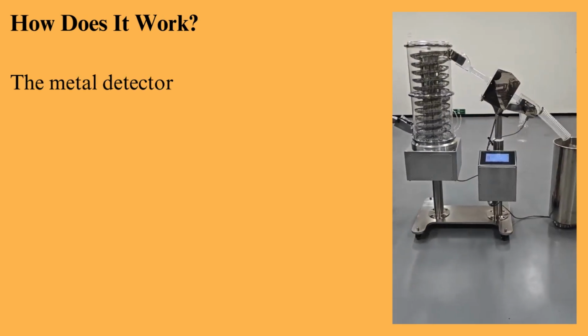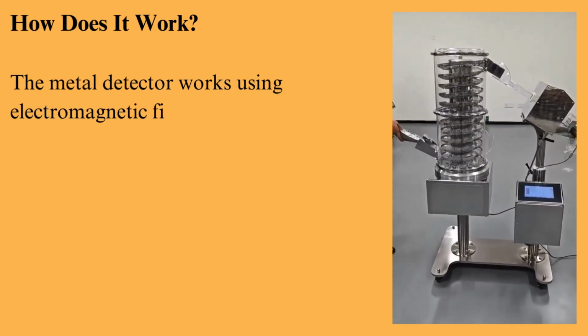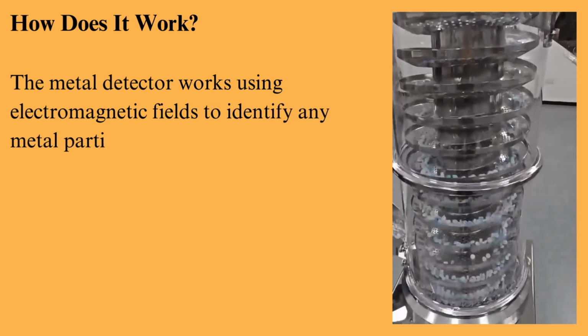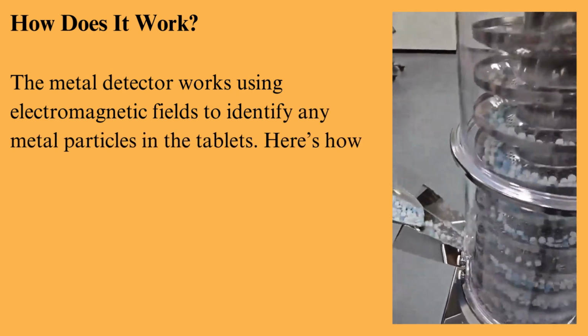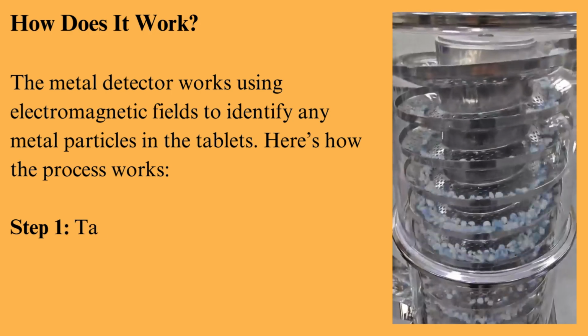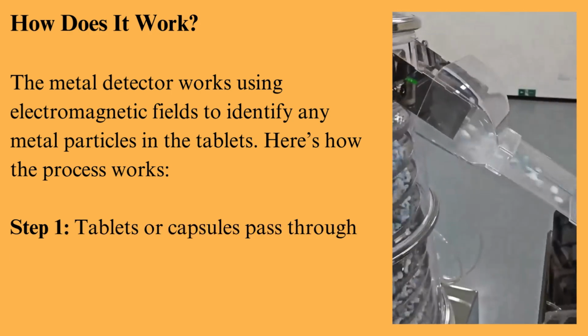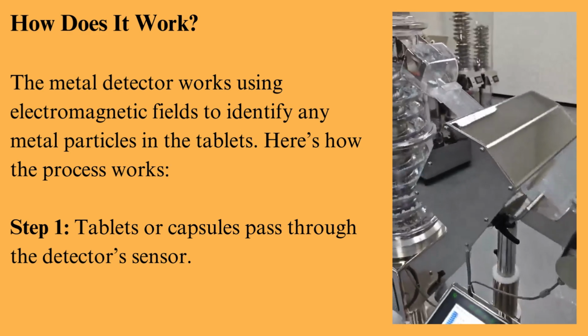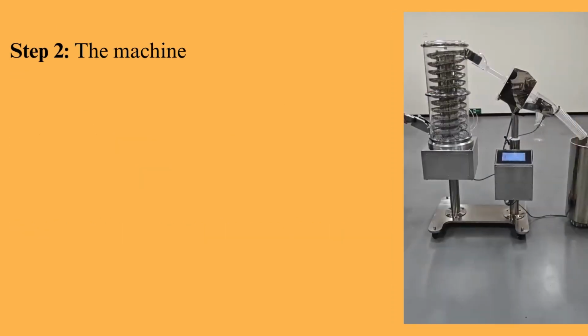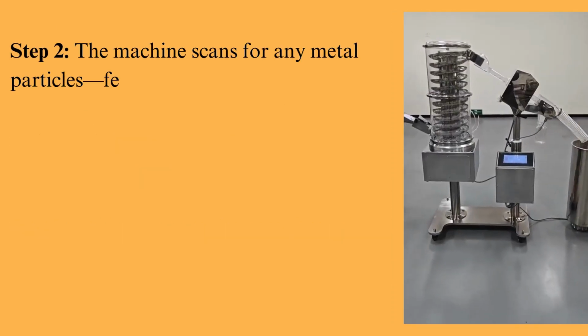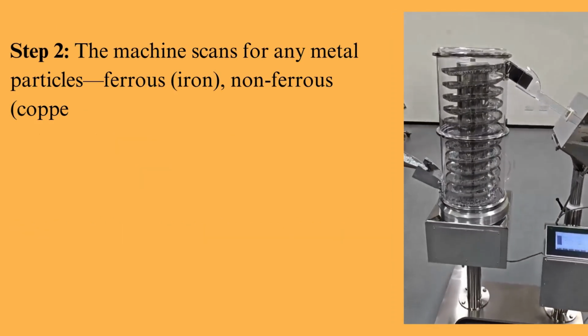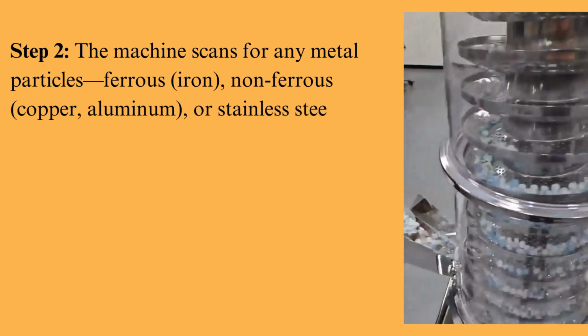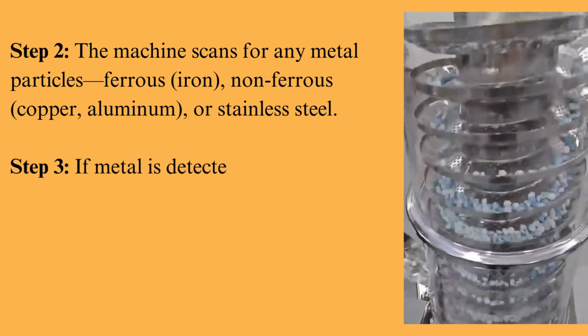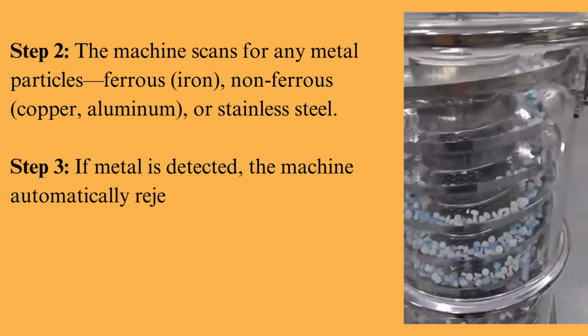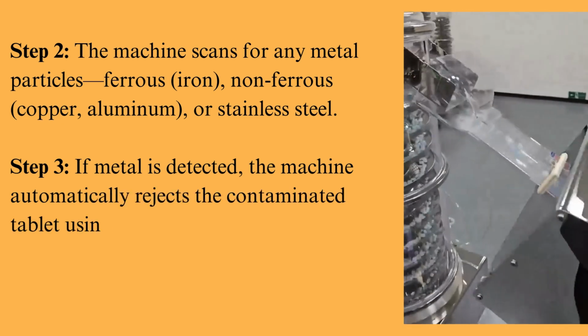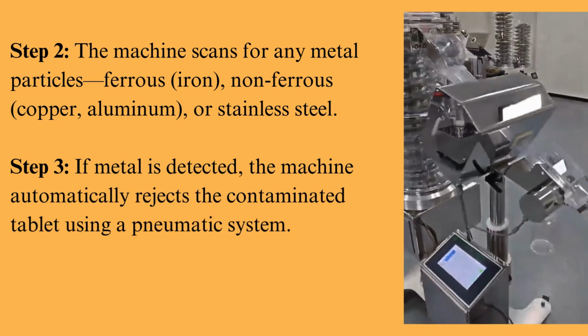The metal detector works using electromagnetic fields to identify any metal particles in the tablets. Here's how the process works. Step 1. Tablets or capsules pass through the detector's sensor. Step 2. The machine scans for any metal particles: ferrous (iron), non-ferrous (copper, aluminum), or stainless steel. Step 3. If metal is detected, the machine automatically rejects the contaminated tablet using a pneumatic system.